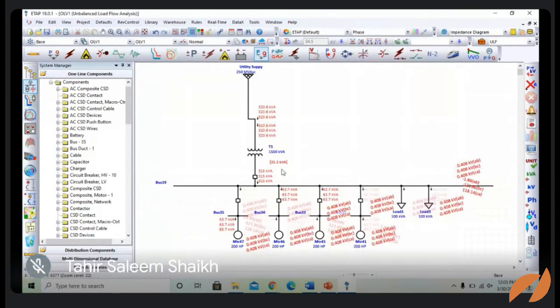And for the AC, you can also check out here the different fuse rating, meter rating, relay. You can also select that if you want to know the ID rating, kilovolt, or if you want to know about the phases, you can also select it. So this is the power flow in each phase from this utility company to the transformer. And this is the loss, 35.3 kVA is the loss at the transformer secondary, and this is the power flowing in each phase from this transformer secondary to the bus.